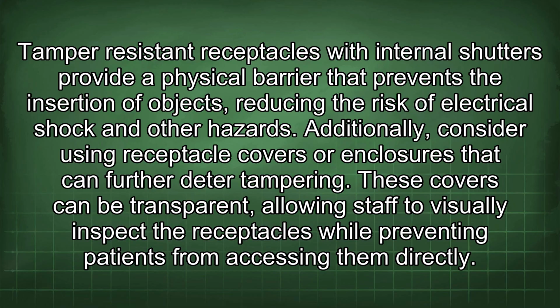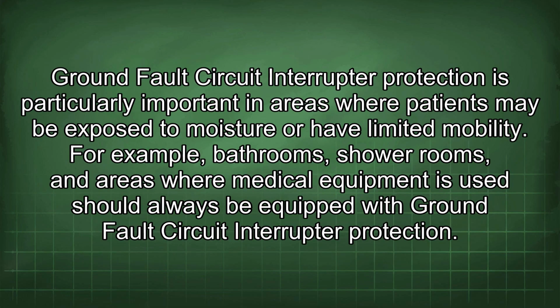Additionally, consider using receptacle covers or enclosures that can further deter tampering. These covers can be transparent, allowing staff to visually inspect the receptacles while preventing patients from accessing them directly. Ground fault circuit interrupter protection is particularly important in areas where patients may be exposed to moisture or have limited mobility. For example, bathrooms, shower rooms, and areas where medical equipment is used should always be equipped with ground fault circuit interrupter protection.